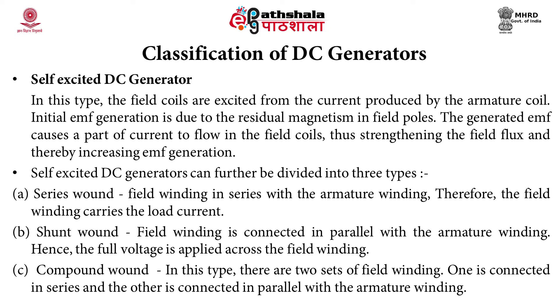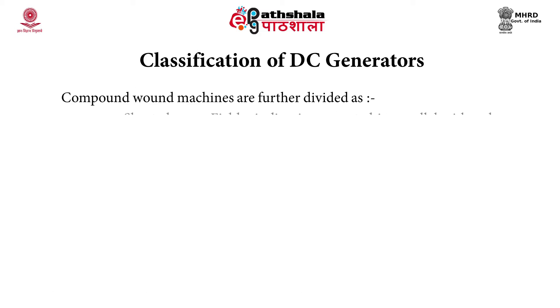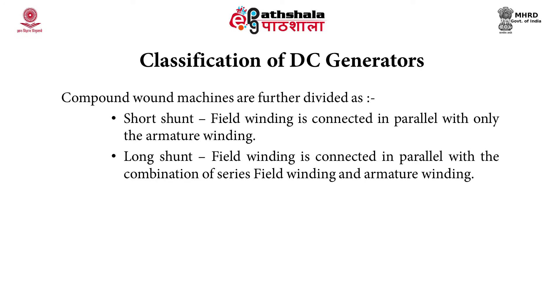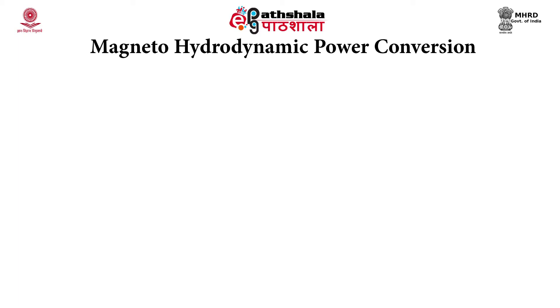In series wound, the field winding is in series with the armature winding, so it carries the load current. In shunt wound, the field winding is connected in parallel with the armature winding, so full voltage is applied across the field winding. In compound wound type, there are two sets of field winding — one connected in series and the other in parallel with the armature winding. Compound wound machines are further divided into short shunt, where the field winding is in parallel with only the armature winding, and long shunt, where the field winding is in parallel with the combination of the series winding.